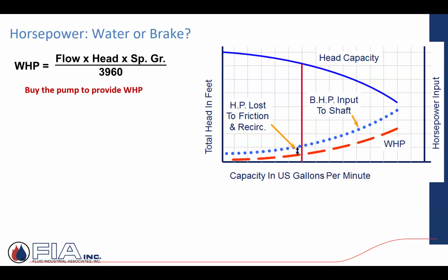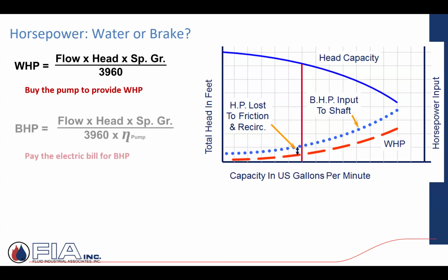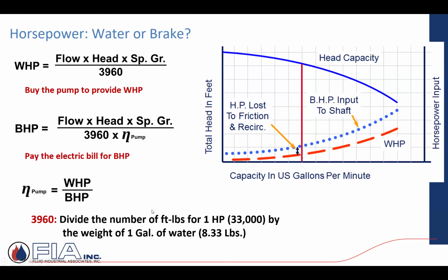Just real quickly, getting into horsepower. There's two different: a water horsepower and a brake horsepower. And all it's saying here is the water horsepower is your flow times head times specific gravity divided by 3960. I'll explain that in a second. That's what's required by the pump to provide the water horsepower. The brake horsepower is what you're paying your electric bill for, because there's an efficiency loss. So you're using a little more horsepower because of some of the efficiency losses. So 3960, all it is, is you divide the number of foot-pounds for 1 horsepower, 33,000 foot-pounds, by the weight of a gallon of water. That's that 3960 factor. What's the efficiency of that pump? You do the calculation, and that becomes your brake horsepower.